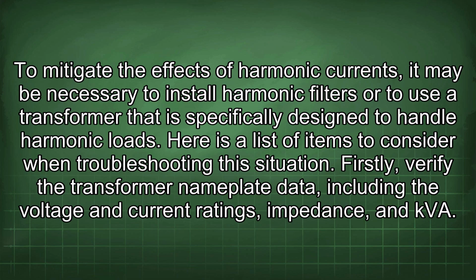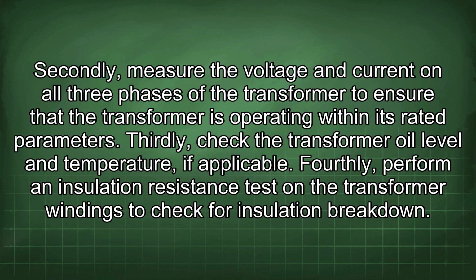Firstly, verify the transformer nameplate data, including the voltage and current ratings, impedance, and kVA. Secondly, measure the voltage and current on all three phases of the transformer to ensure that the transformer is operating within its rated parameters. Thirdly, check the transformer oil level and temperature, if applicable. Fourthly, perform an insulation resistance test on the transformer windings to check for insulation breakdown.